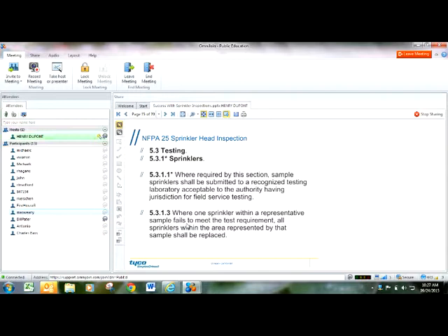So that sample is rejected for the entire building. If they would have come back normal, then every sprinkler head in their building would have been fine for another 10 years when it has to be tested again. If any one of those 4 sprinkler heads fail, every sprinkler head within that sample is considered failed, and then they have to replace every sprinkler head in the building.